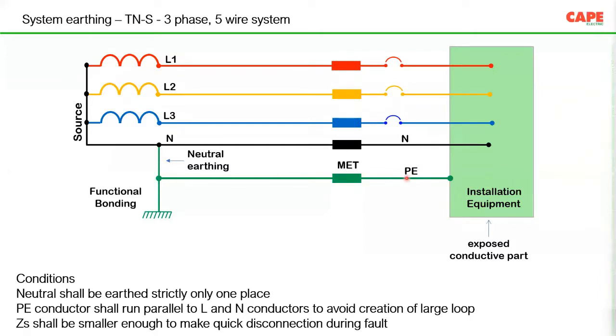So this is a TN-S system. Basically, it's a 5-wire system. And the neutral is also earthed, which is a functional bonding. Functional bonding in the sense that, in order to create a stable voltage in your electrical wires to earth, a functional bonding is created. So basically, this is called a TN-S system, meaning a 5-wire system. Neutral shall be strictly earthed only at one place. That means strictly only at one place. You are not supposed to connect the neutral at multiple places. Then you will have bigger problems.